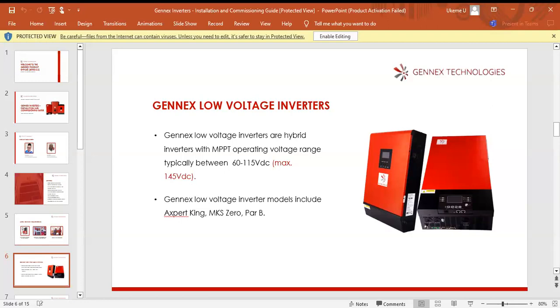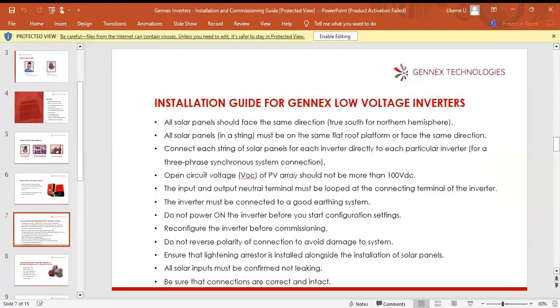Gennex low voltage inverter models include Axpert King, MKS Zero, then Par B. Some of us are familiar with these models. The King works like a UPS, it is an online inverter. MKS Zero has zero transfer time, while Par B is line interactive and switches within a few microseconds, and you just don't notice that transfer time. But the first two are zero transfer models. Installation guide for Gennex low voltage inverters.